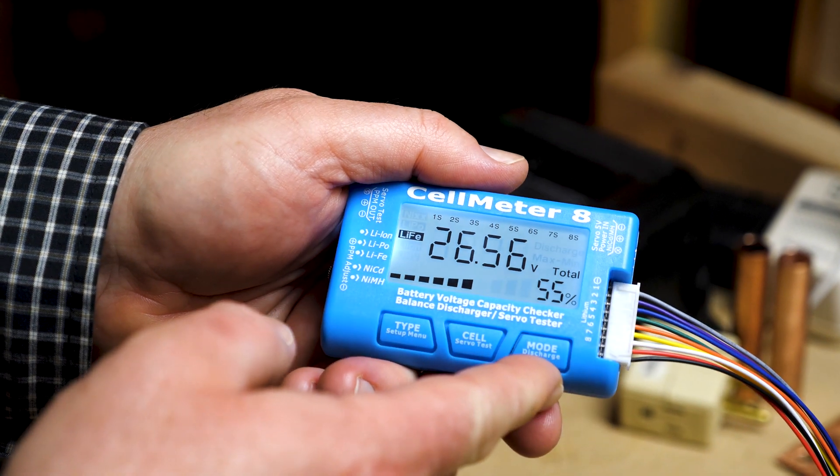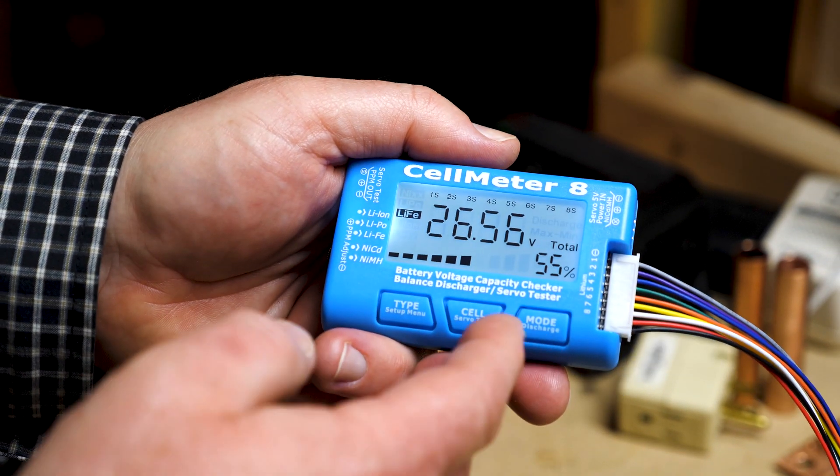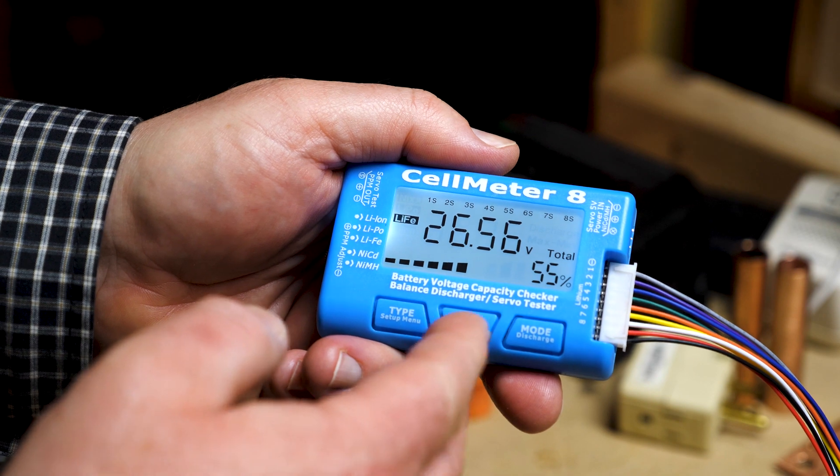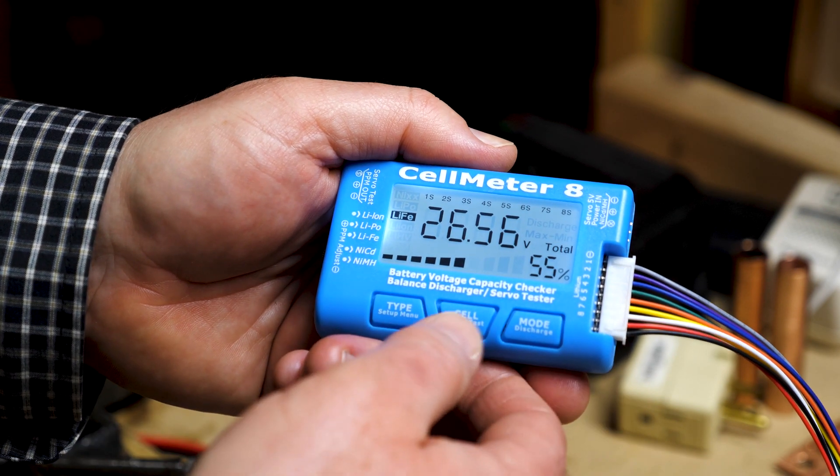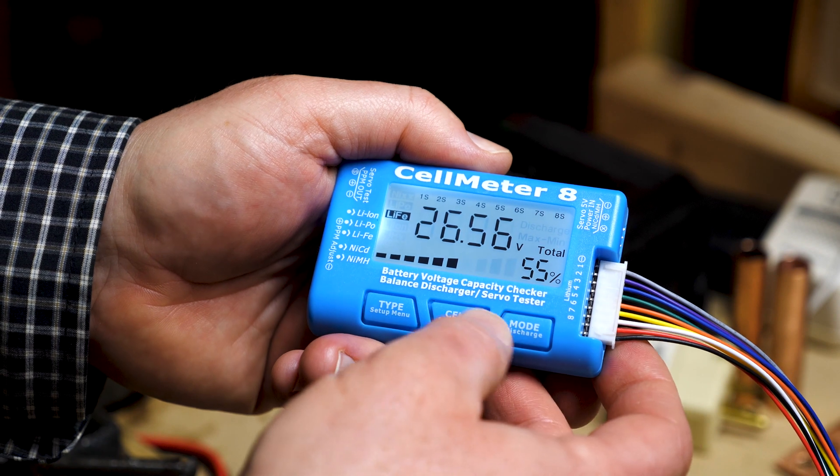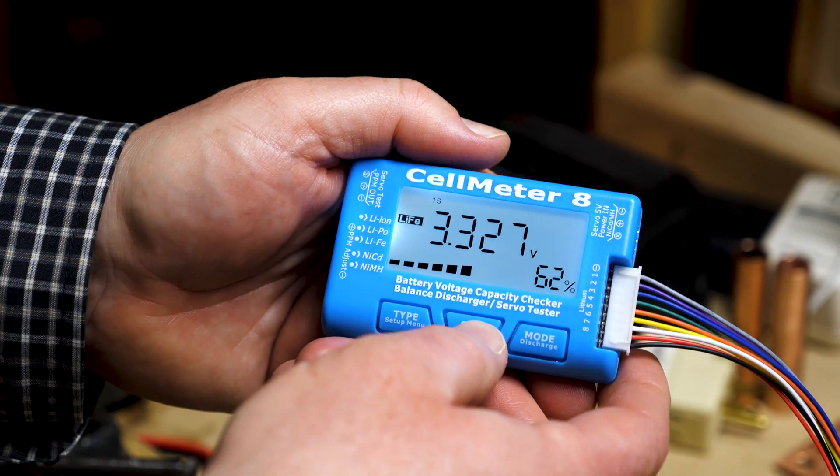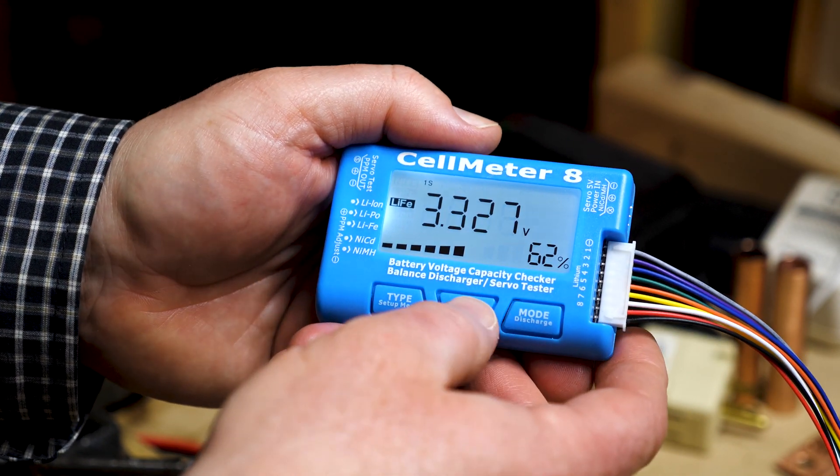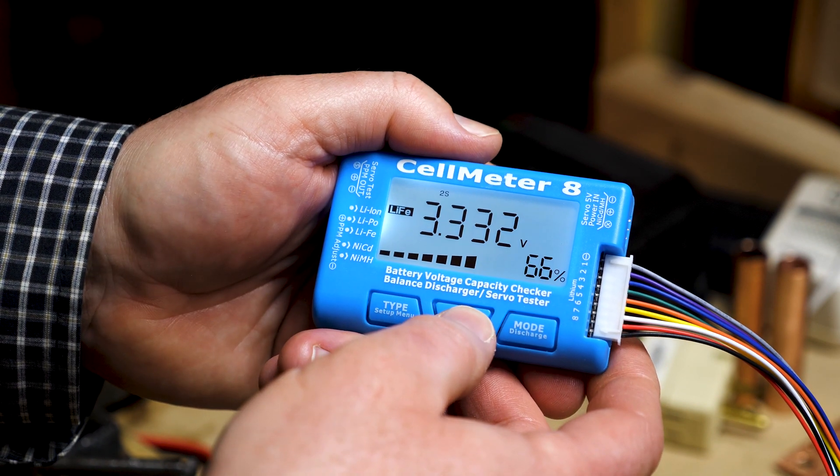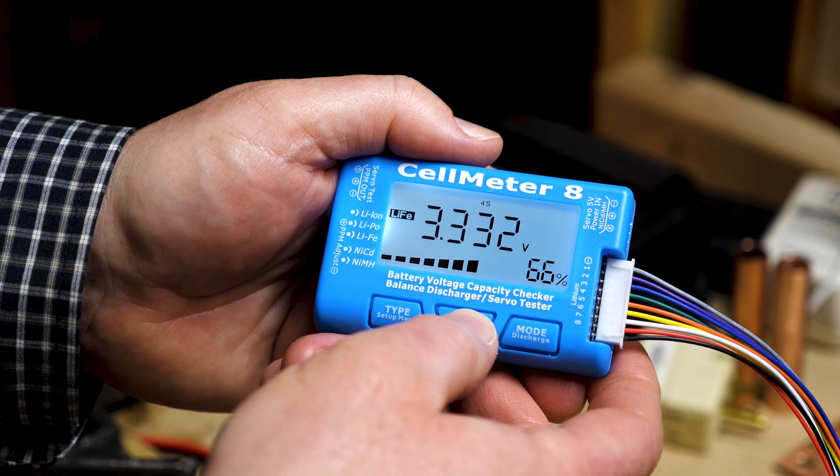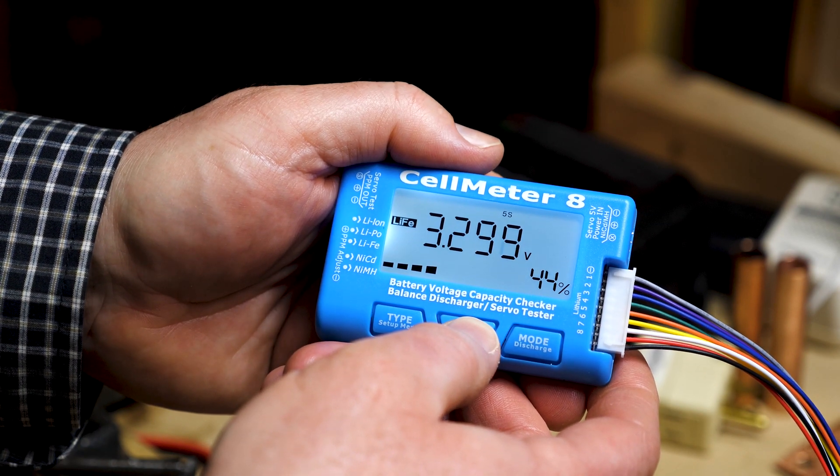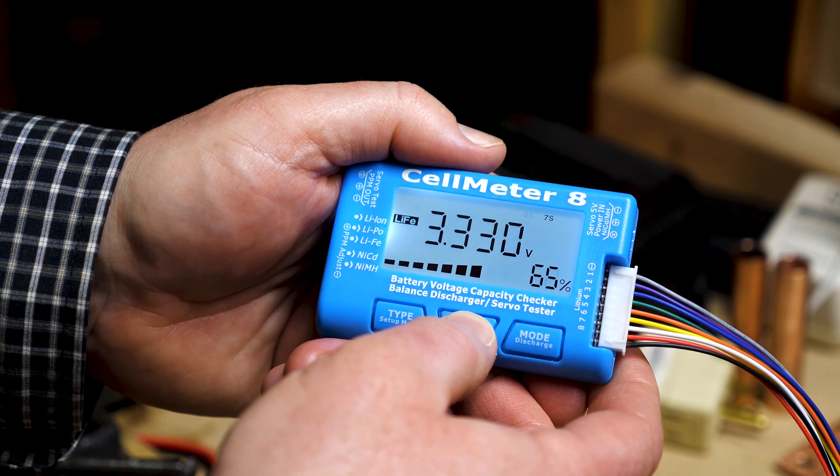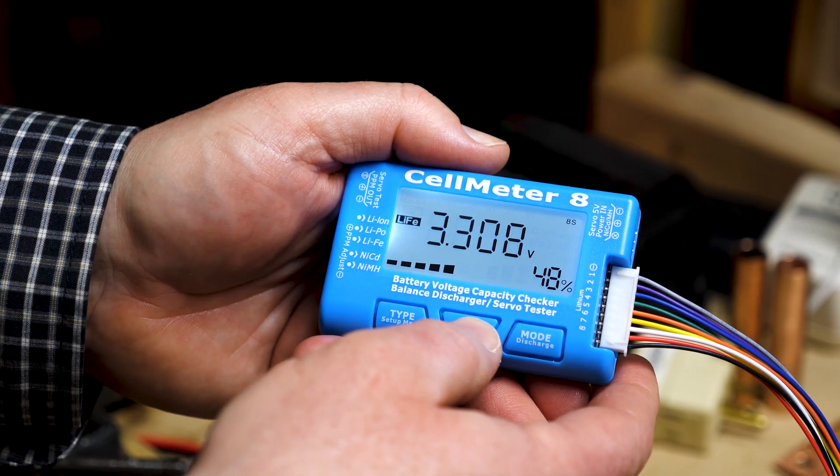Take a look at the voltage on my cell meter. You can see the overall voltage is 26.56 volts. The battery's not currently being charged, it's just at rest. If we take a look at each individual cell, things are looking pretty good or so it seems. First cell's 3.3, going through they're all pretty close to 3.3, so one would think the battery's in pretty good shape.